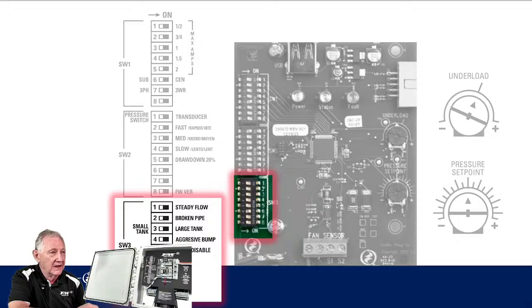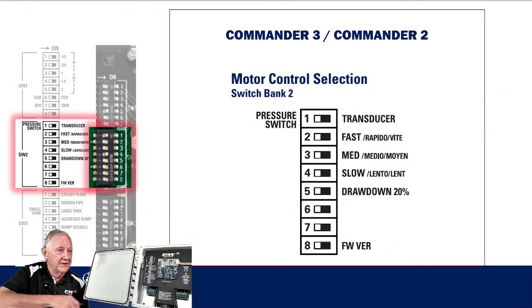I want to go back to this second bank here. So basically you're setting either for a pressure switch or a pressure transducer. Those positions 2, 3, and 4 have to do with response time. Now, oftentimes those never have to be messed with, all right? So there are occasions, though, that if we want to increase the response time, we can do that.